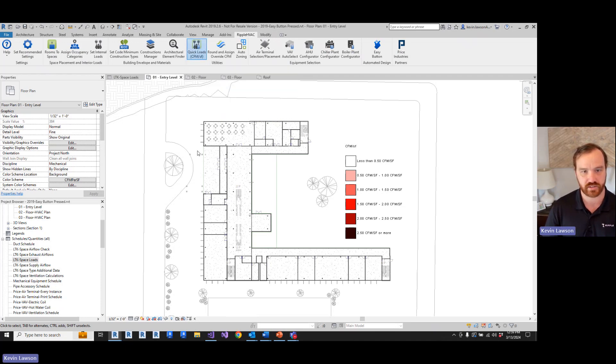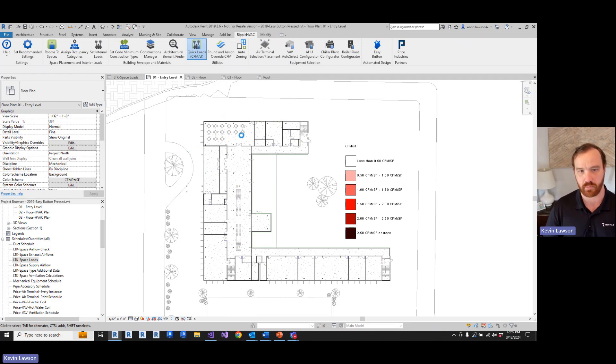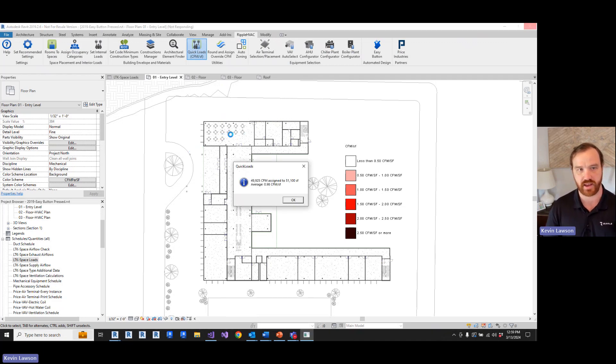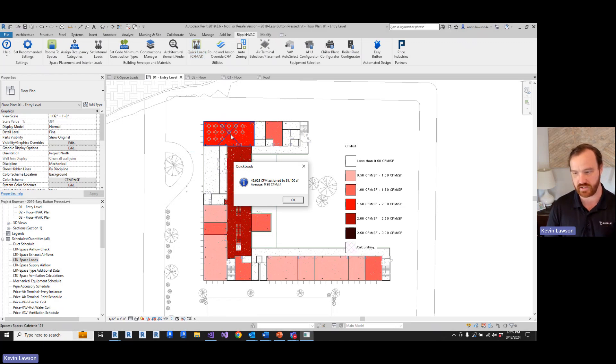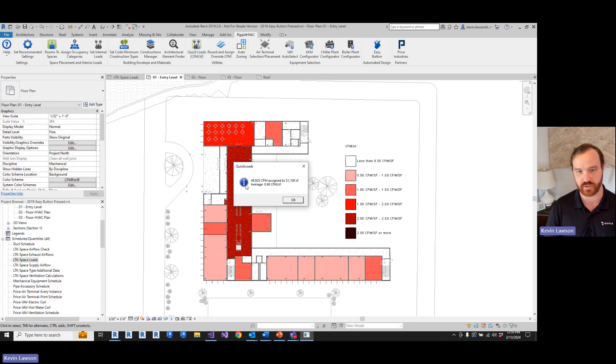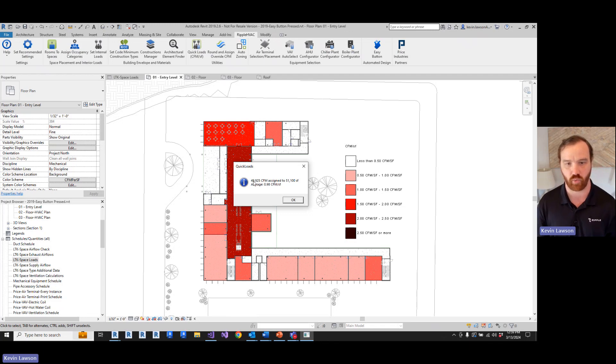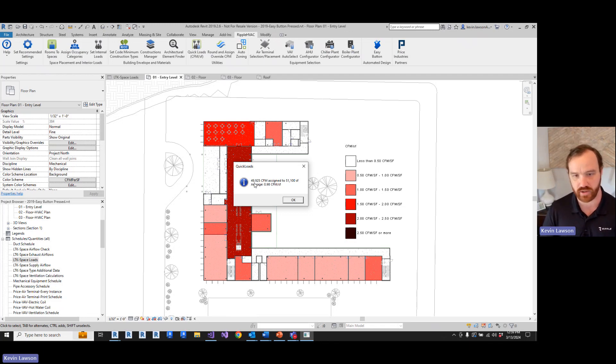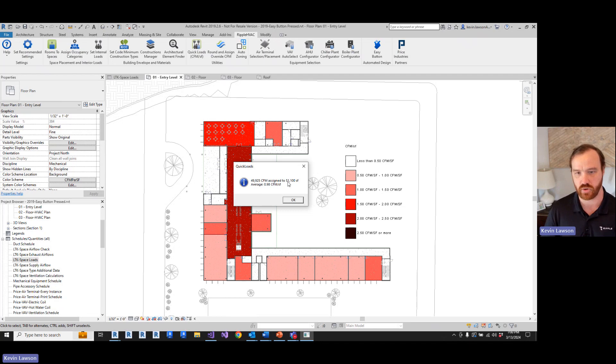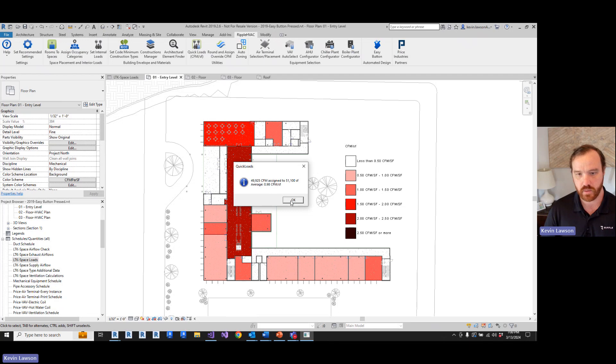Depending on where you are in the country, it's going to adjust its rule of thumb assumptions. So we're gonna hit this, it's going to go through the whole project, make the calculations, add up the internal loads, add this default exterior load factor. It applied about 50,000 CFM to about 51,000 square feet, which is a little bit less than one CFM per square foot.